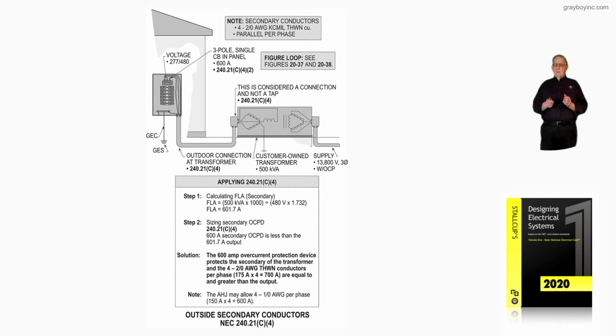13,800 volt with a 3-phase overcurrent device, back maybe in a substation or from one building feeding this building from a main building. But the main thing, we have a main ahead of that primary, but we're tapping off of the secondary, and there's no requirement for length until you enter into the building from that secondary side. Now, this is customer owned. It's a 500 kVA transformer.